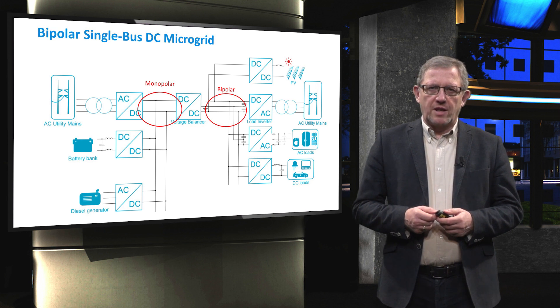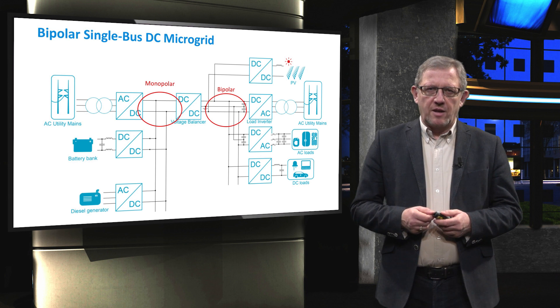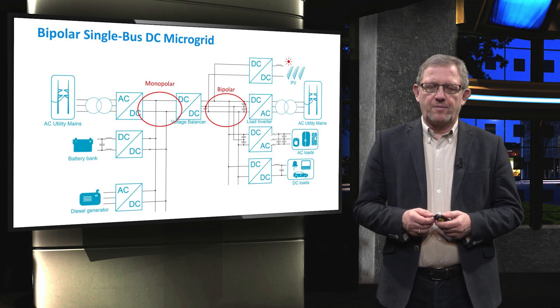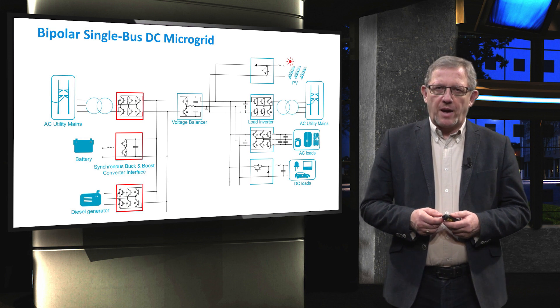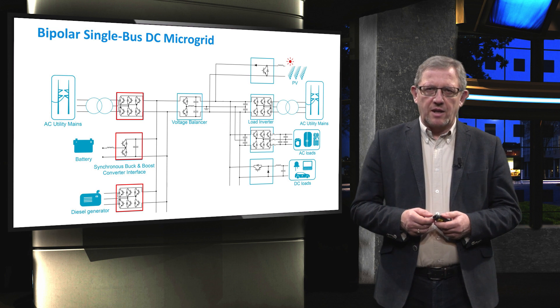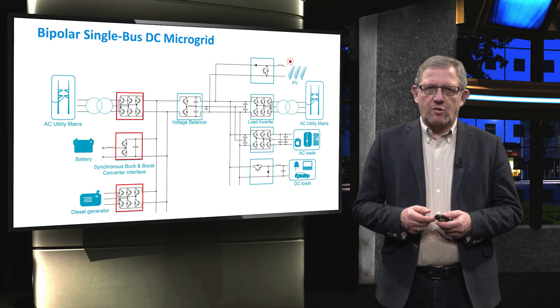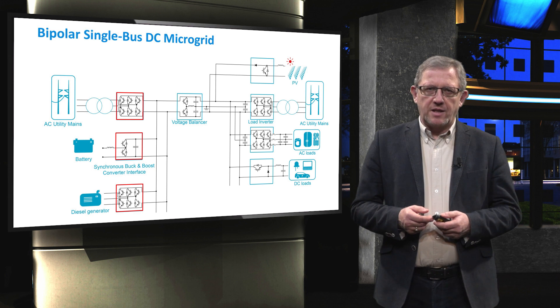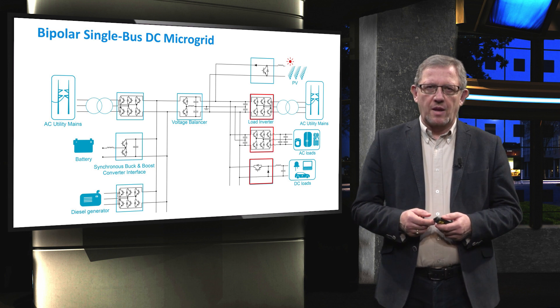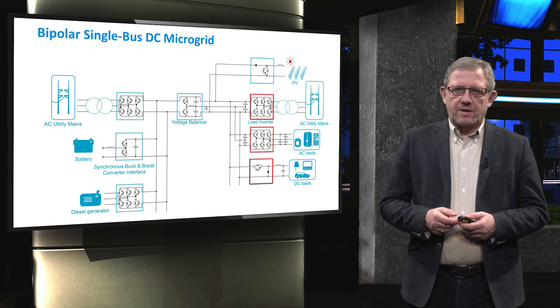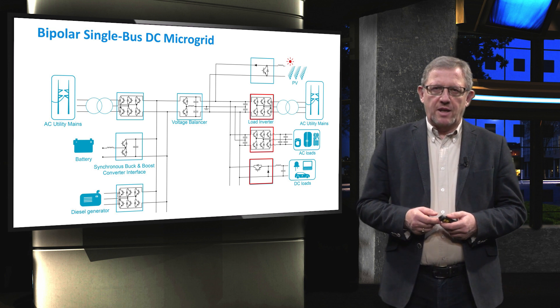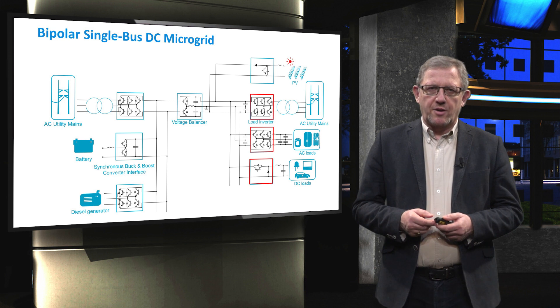In the monopolar DC link on the left, the main grid is connected through a three-phase, three-leg voltage source inverter or AC-to-DC converter. The battery bank is connected to the monopolar DC link with a buck-and-boost DC-DC converter. Also, the diesel or gas generator is connected to the DC link via a three-phase AC-DC inverter. On the other hand side, the bipolar DC link is also connected to an external electrical network through an AC-DC voltage source inverter.